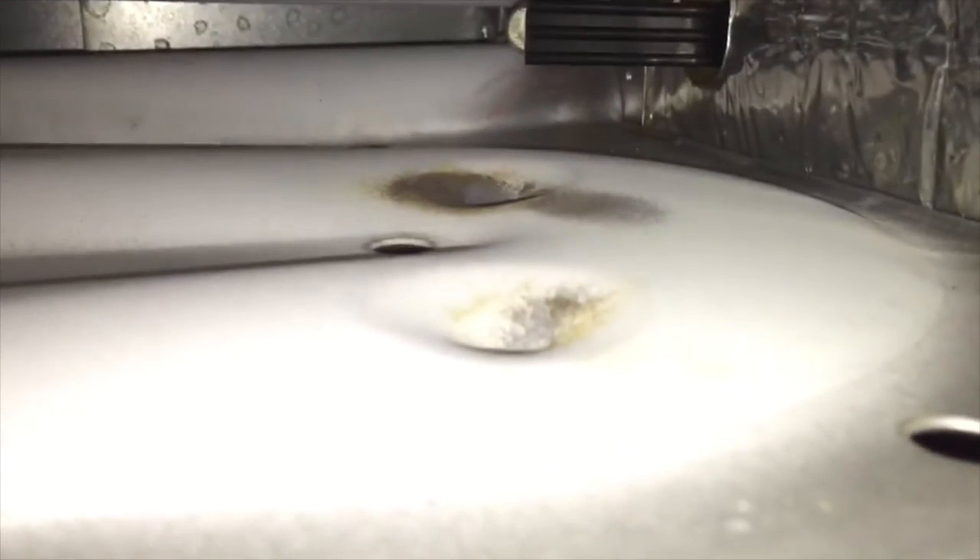The excess air came up to roughly 78%, but did not rise any further. I inspected the heat exchanger as much as I could to confirm if there were any cracks or holes in it, and as you have seen in the video, it is not in perfect condition, but I was unable to find any kind of cracks or holes. Definitely several spots that were not in the greatest condition, but nothing definitive to say yes indeed there was a hole.